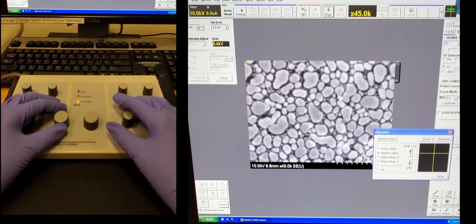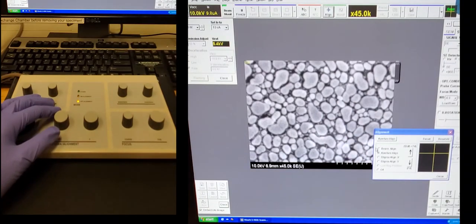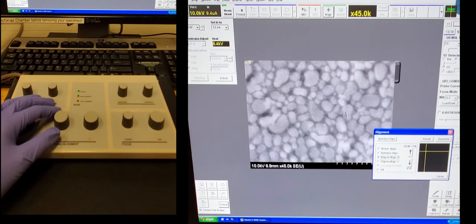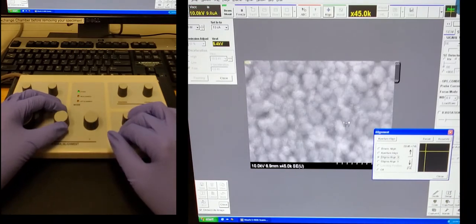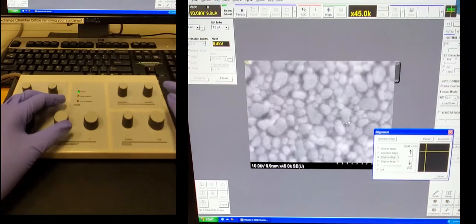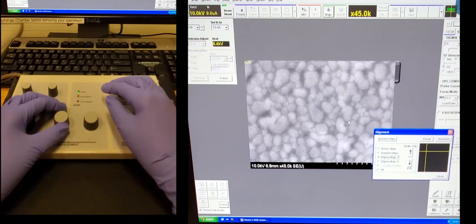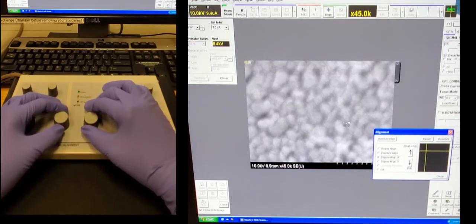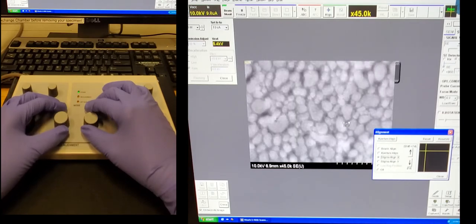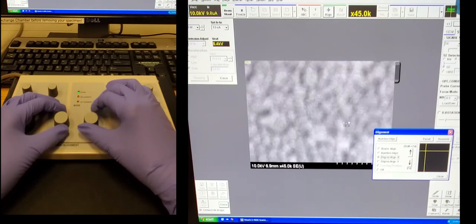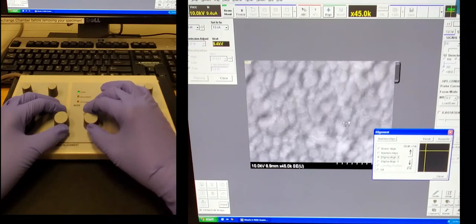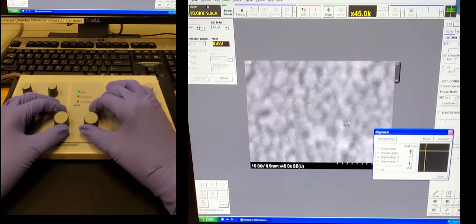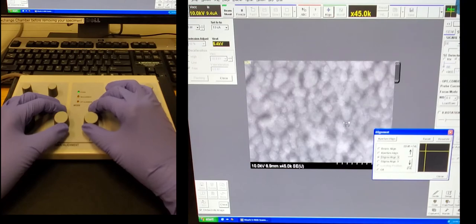So you can make an adjustment and then look at the image, see if it got better. If it got better then you're going in the right direction. If it starts to get worse then you should stop or go back. Next you can move down. The goal is the same to minimize the wobble in both x and y direction. It will not be as perfect as the last one though, so don't worry too much about that. You can see it was getting worse. So we went too far.